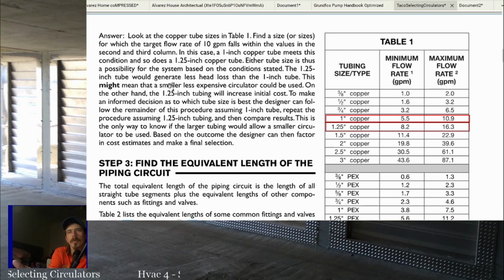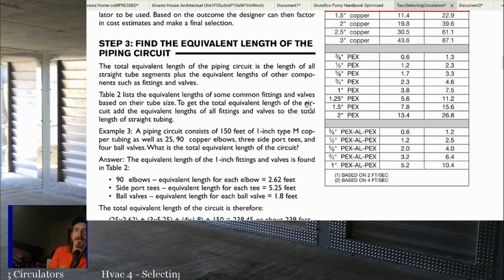So to make an informed decision as to which tube size is best, you can follow the remainder of the procedure assuming 1 inch, and then repeat the procedure assuming 1.25 inches, and then compare your results. This is the only way to know if the larger tubing would allow a smaller circulator to be used. So you might get to the end and you'll need the same circulator either way, in which case why not go 1 inch, right? But you might get to the end and find out, oh, I need this pretty expensive, hard to find off the shelf circulator, so it's not worth using the smaller pipe at that point. So based on that outcome, you can figure out what you need.